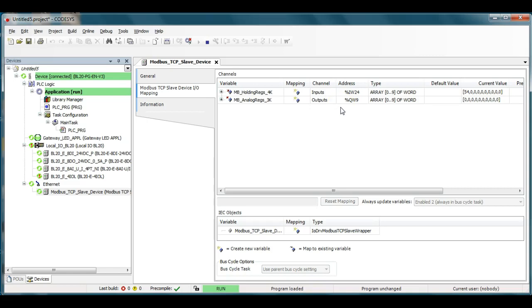The holding registers from the BL20 is going to be output data that is coming from a master to the BL20 and the analog input registers the 30000 series will be what goes from the BL20 to the Modbus master. Hope that clarified some things. Hey thanks a lot, have a great day, see ya!